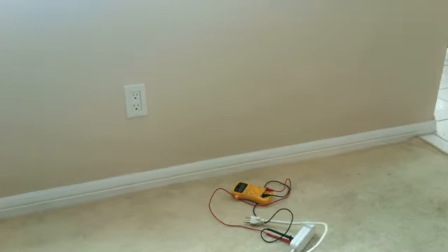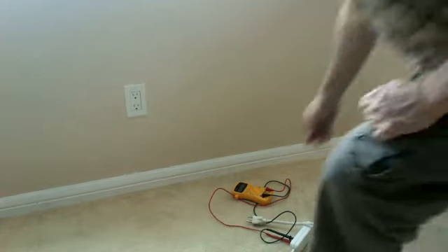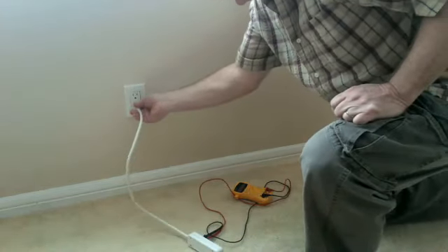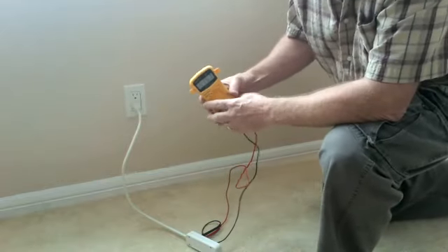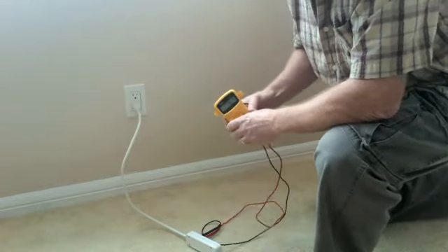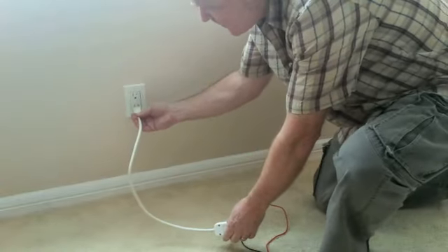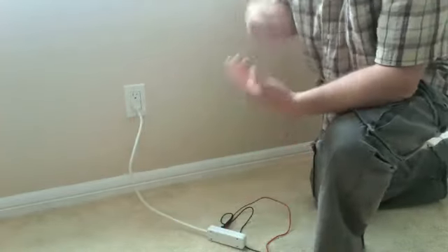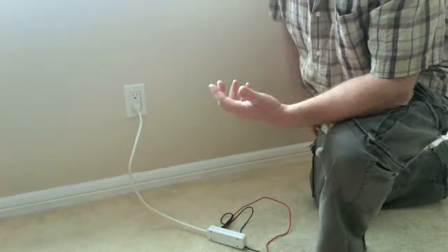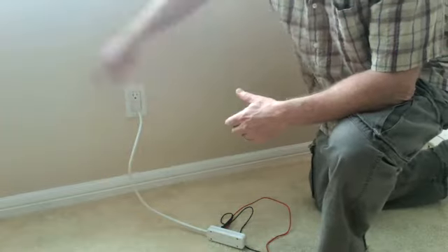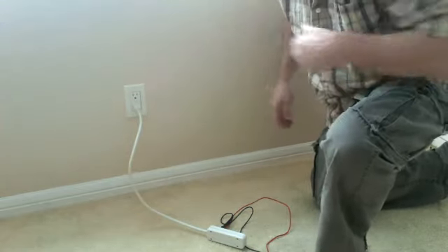Okay, here we are with outlet number 3. The voltage I'm reading on this outlet is 115.7. That's almost the same thing. 115.7. So I don't see any difference between the voltage drop at this outlet and the voltage drop where my heater is plugged in. That indicates to me that this outlet is downstream of the other outlet. Let me go bring the heater here.